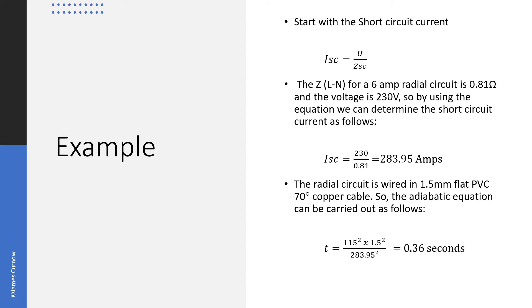If we assume that the radial circuit is wired in 1.5 mm flat PVC 70 degree copper, the adiabatic equation can be carried out as follows: T equals 115 squared, where 115 is the K value for 70 degree copper, multiplied by 1.5 squared divided by 283.95 squared, which gives us 0.36 seconds.